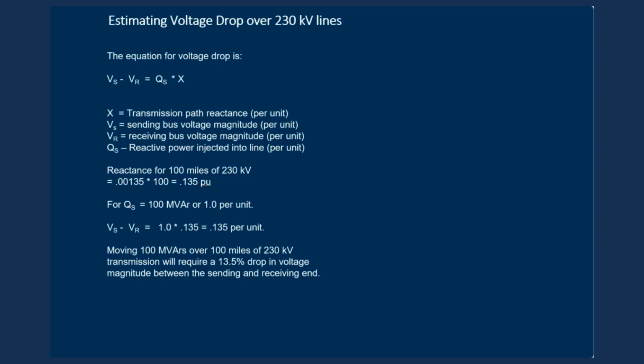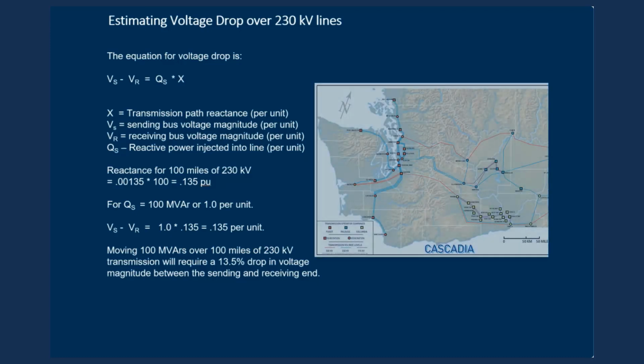In other words, if we move 100 megavars over 100 miles of 230 kV, we should expect a 13.5% drop in the voltage magnitude between the sending and the receiving end. This equation works very well for the Cascadia system.